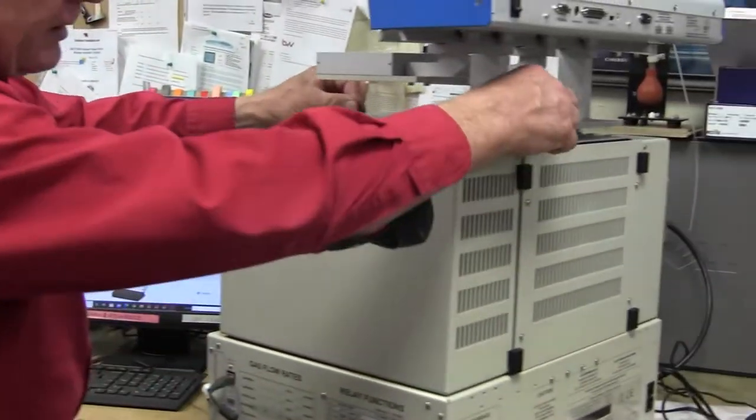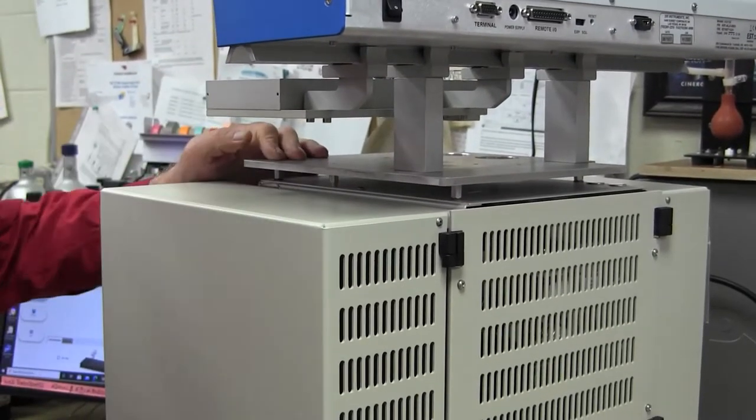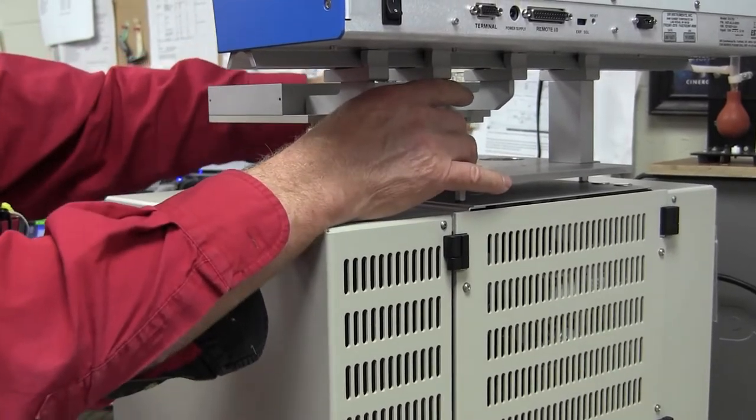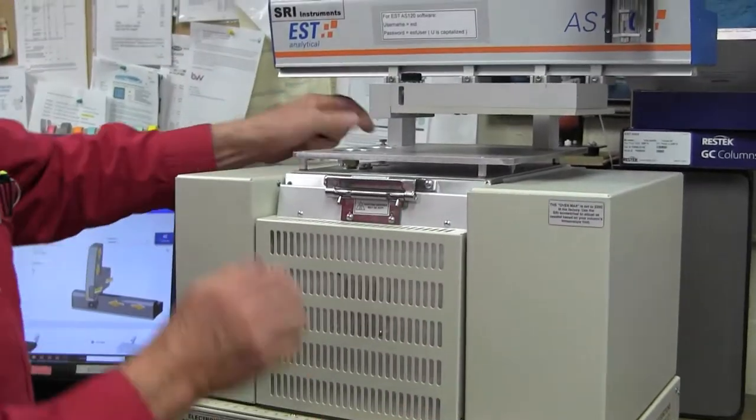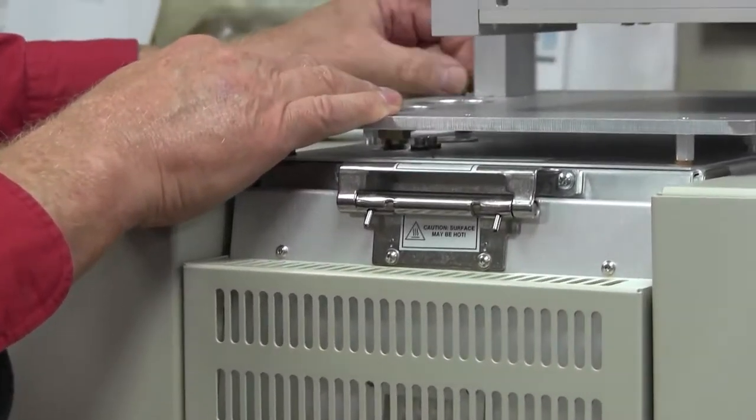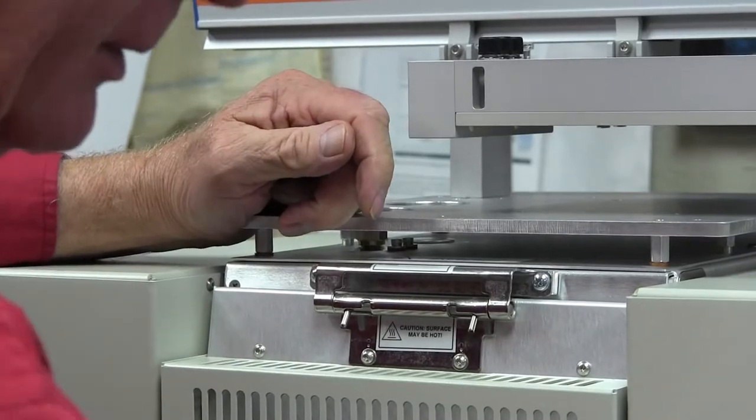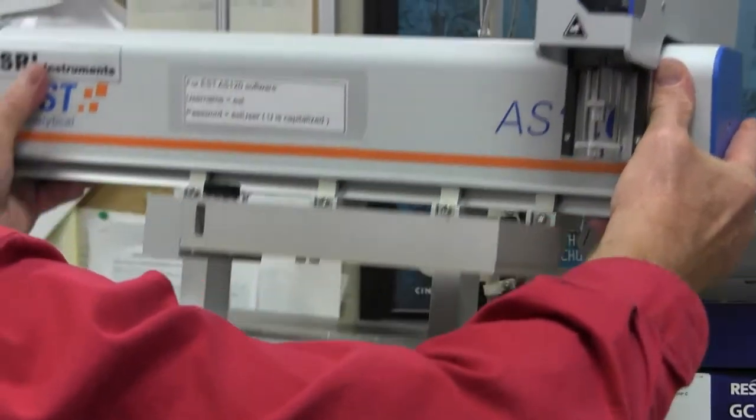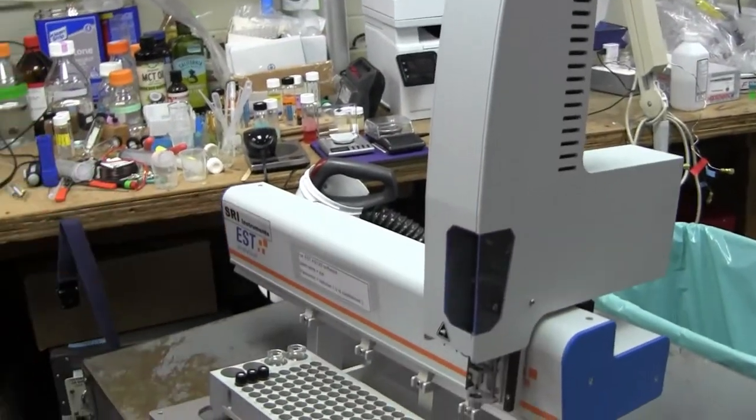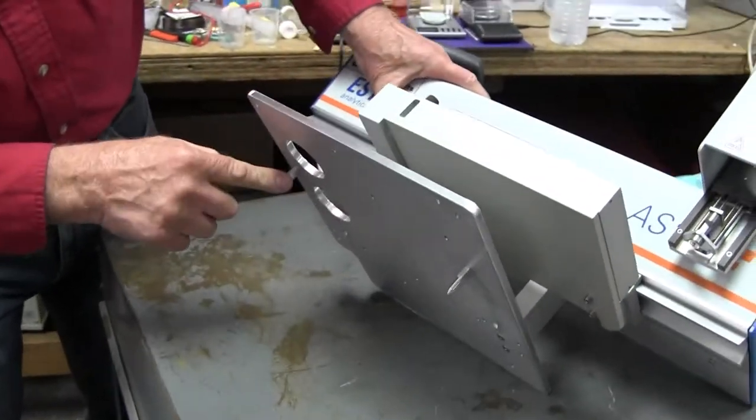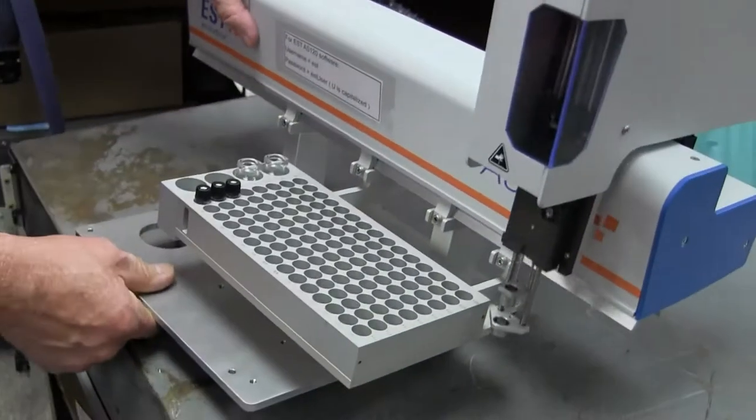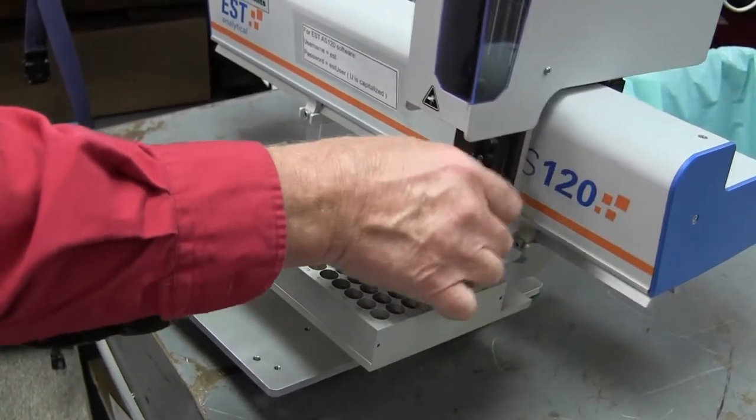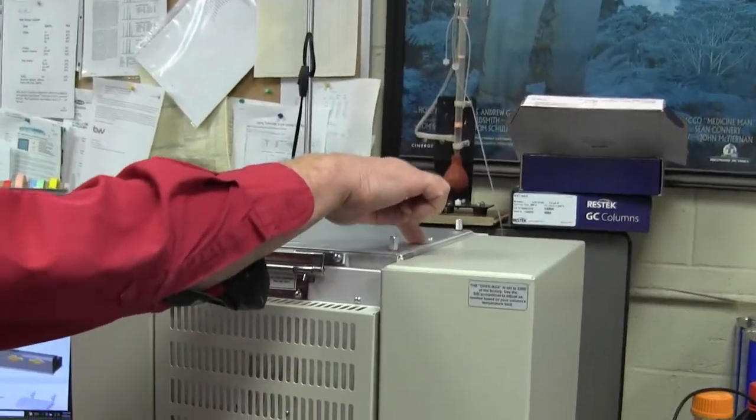So now there's no electrical connections and there's these four brass thumb screws that hold the auto sampler on. So they look like that and there's four of them. Okay, so we've got our four thumb screws. And then I should be able to just lift the auto sampler up and we'll put it on this little bench temporarily. Notice that there's two little prongs at the bottom of this aluminum plate. And those line the auto sampler up like that. So there's two corresponding holes in this plate here on the top.